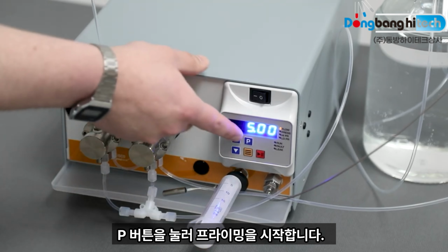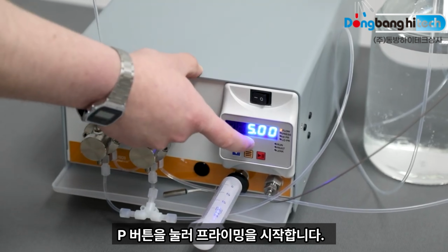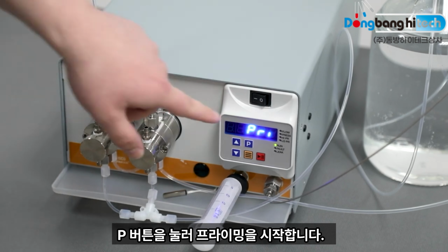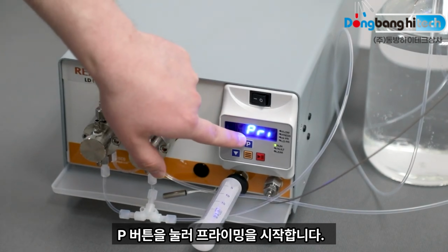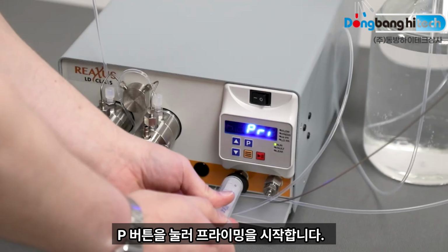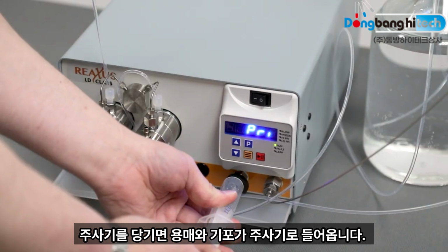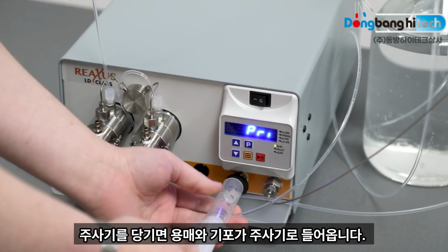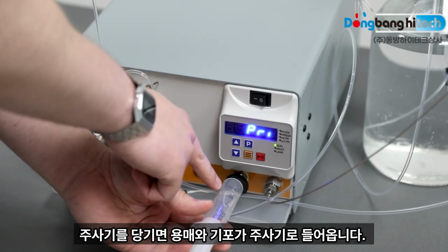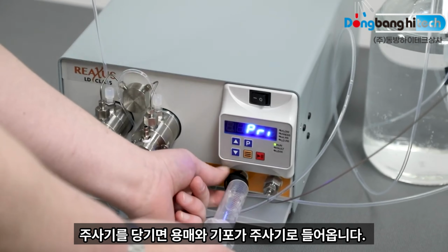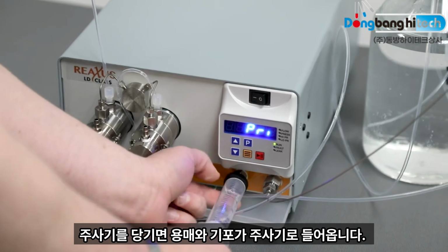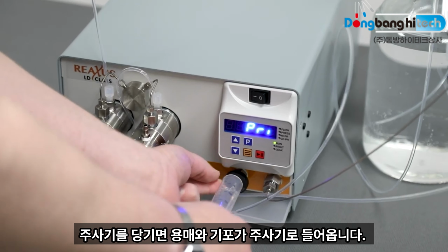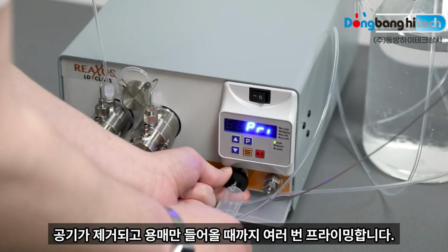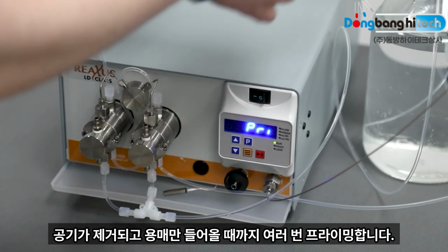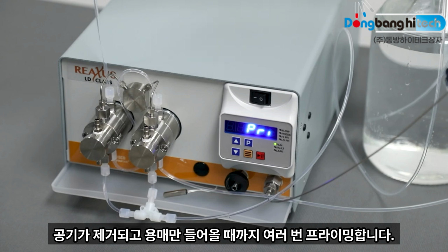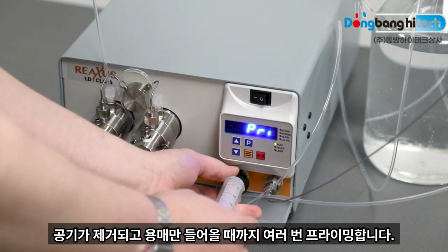And on screen, I will have a P button that I'll press for prime. You should see an indicator telling you that we are now priming. And I will pull on the syringe, and I should start to see solvent and bubbles entering the syringe. You may need to prime several times until you are just pulling in your solvent into the syringe.